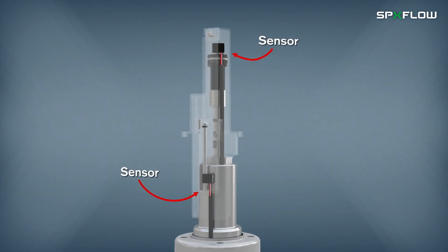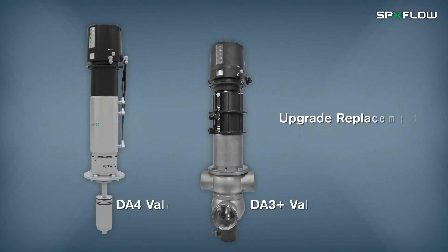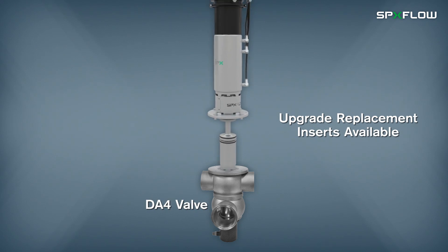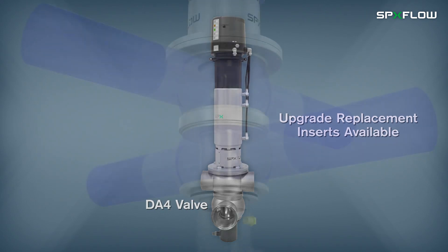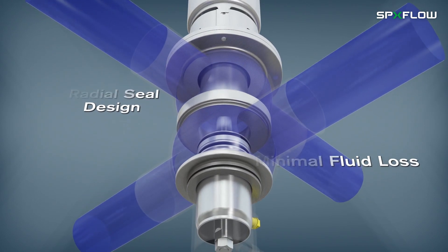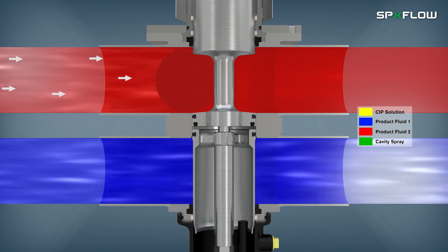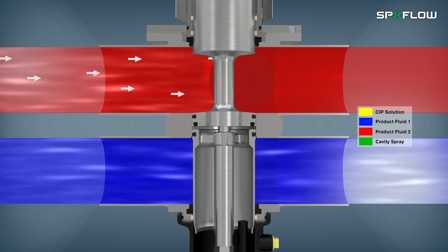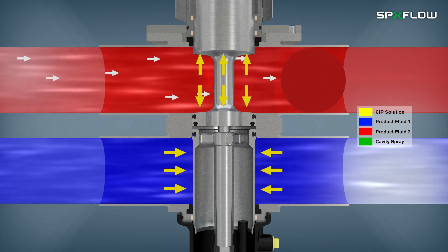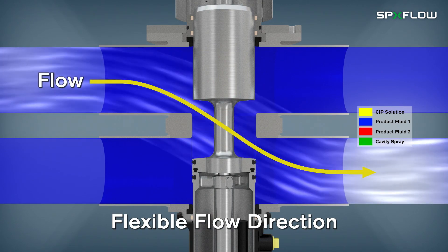Sensing of all positions occurs from the top of the valve. Replacement inserts are available to easily upgrade existing installations. A radial seal design provides minimal losses of product fluids during switching. DA4 valves are highly reliable with a fully balanced design and a large leakage cavity that helps prevent hydraulic blocking, withstand pressure spikes, and enable a flexible flow direction without slamming.